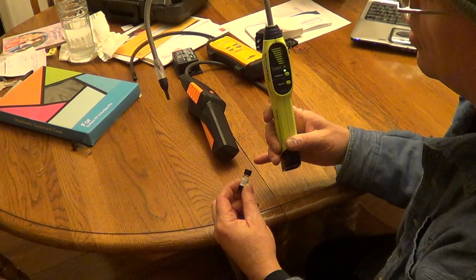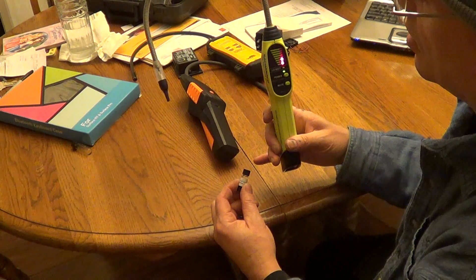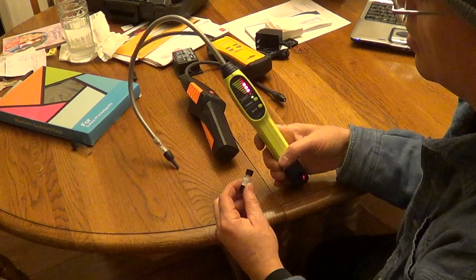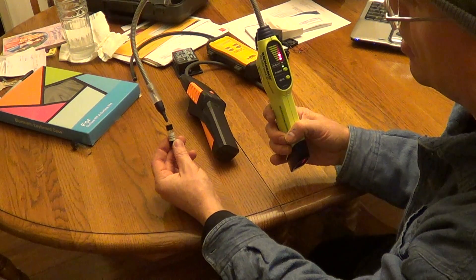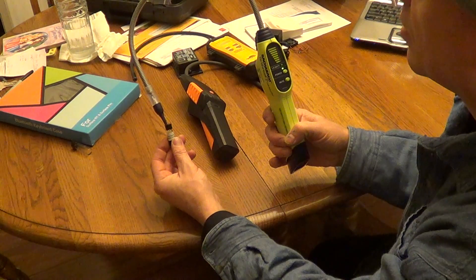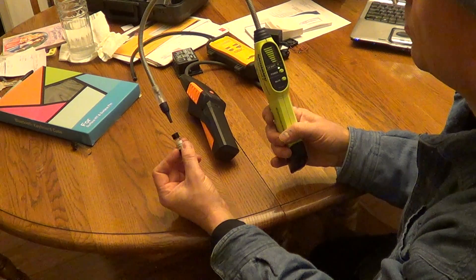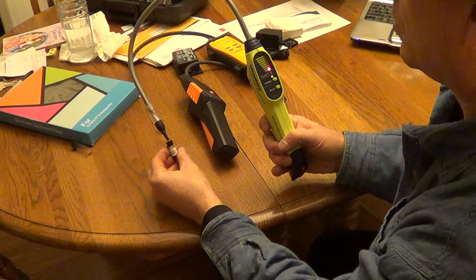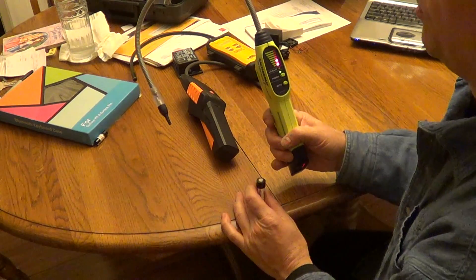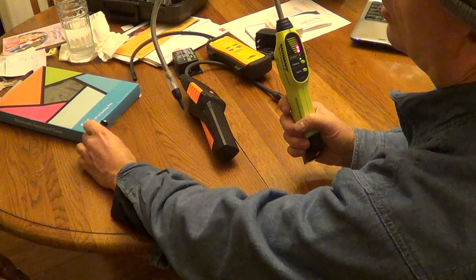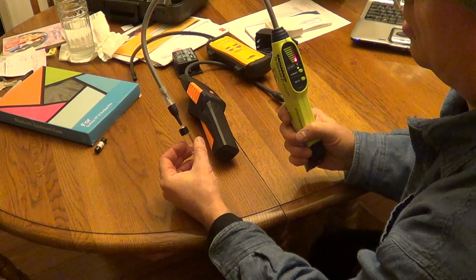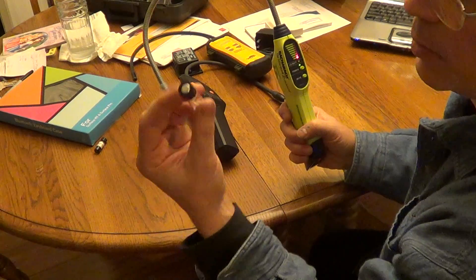And make sure we don't have any nuisance. That's okay. Now this Bacharach's really not even picking up the HFC at all. It's hard to distinguish is it picking it up or is it just doing a nuisance. And then remember the SRL-8 picks up the HFC about two inches away. So this one's picking it up about an eighth of an inch.